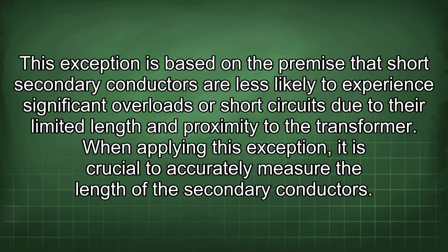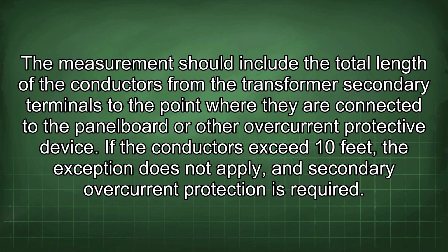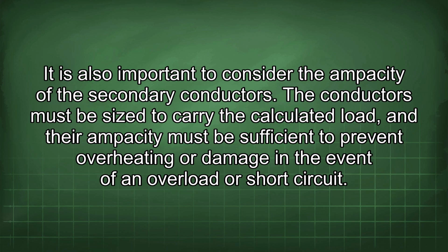When applying this exception, it is crucial to accurately measure the length of the secondary conductors. The measurement should include the total length of the conductors from the transformer secondary terminals to the point where they are connected to the panel board or other overcurrent protective device. If the conductors exceed 10 feet, the exception does not apply, and secondary overcurrent protection is required. It is also important to consider the ampacity of the secondary conductors.